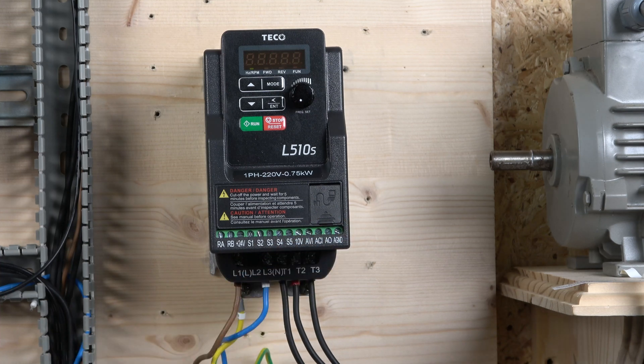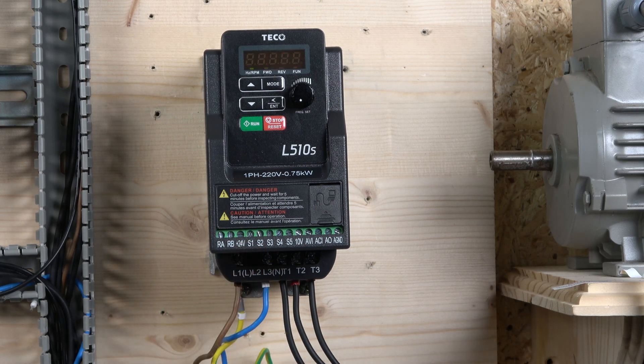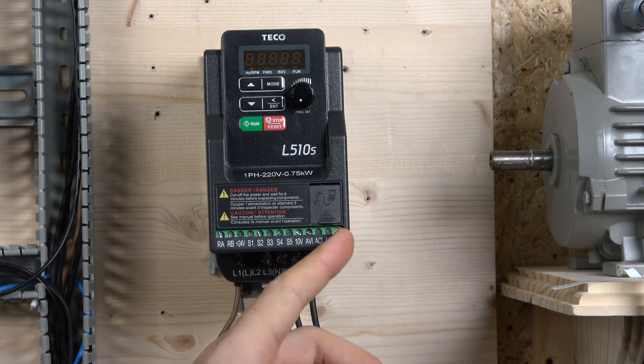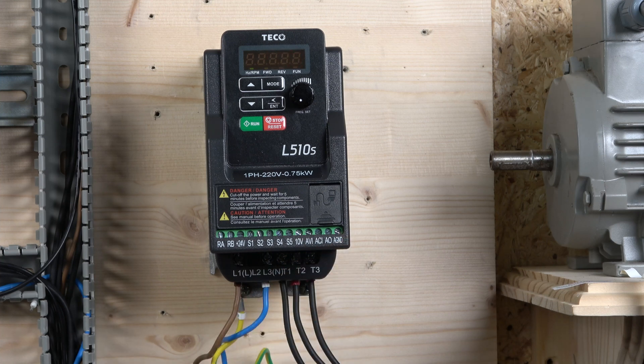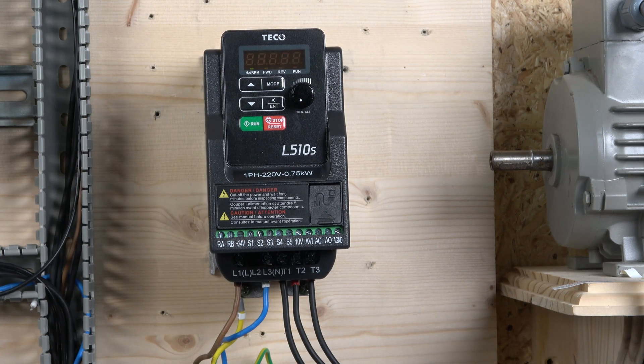On the front terminals, there are five configurable inputs which we'll be using a lot in upcoming videos. RA and RB are relay outputs. There's a 24-volt terminal to power up all the inputs. The section from 10 volts to ground is dedicated for analog input and output. There's also an RS485 port which you can connect to a laptop — we'll look into that software in the future.